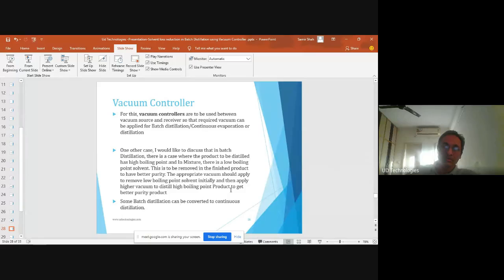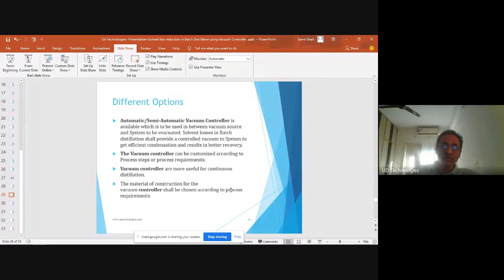However, some batch distillation can be converted into continuous distillation. So what are the options available for the vacuum controllers? Automatic or semi-automatic vacuum controllers are available, to be used between the vacuum source and the system. They reduce solvent losses in batch distillation and provide a controlled vacuum to the system to get efficient condensation, resulting in better recovery. The vacuum controller can be customized according to the process steps and process requirements. Like in process steps, there will be some boiling point difference, and low boil solvents are there. There are certain process requirements. The vacuum controller is basically an instrument, so that instrument can be customized.